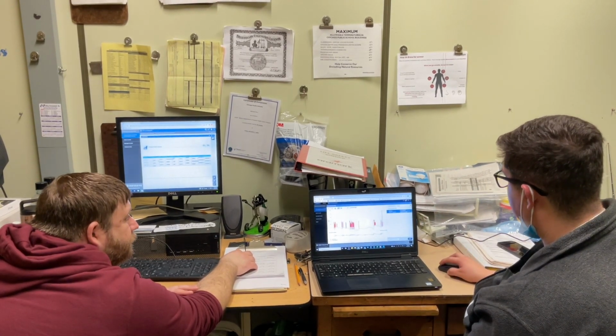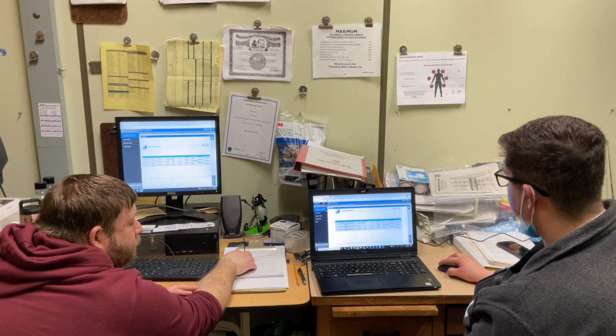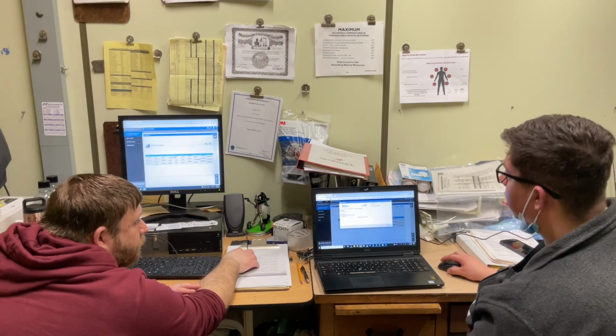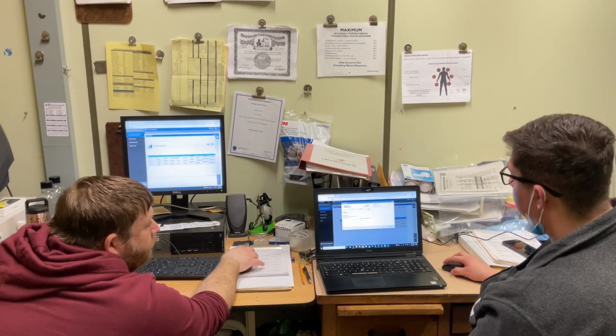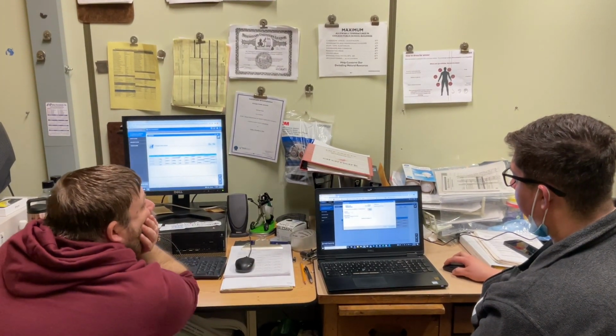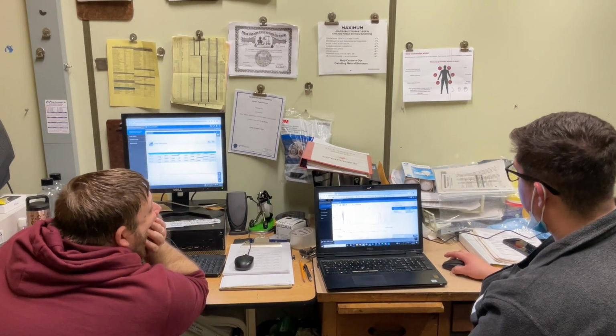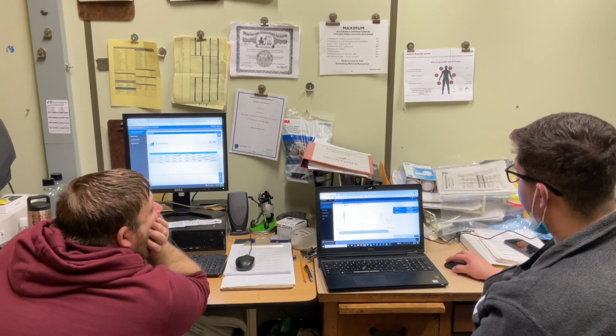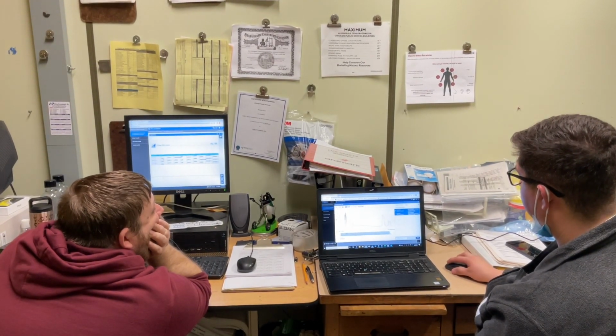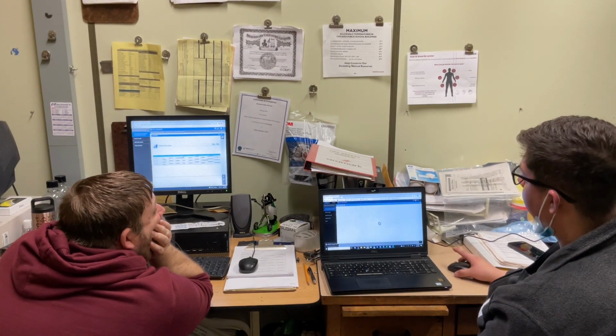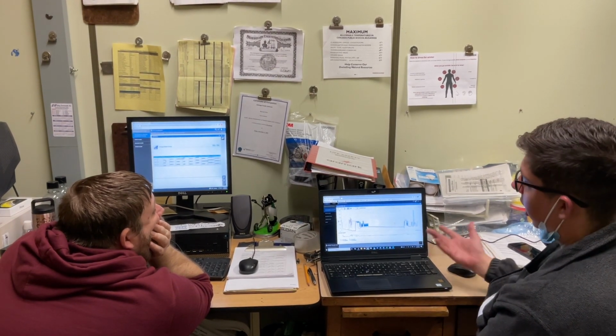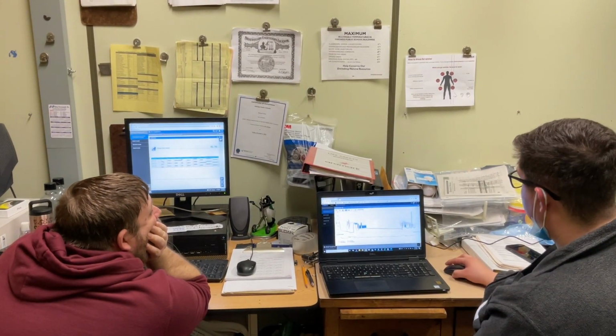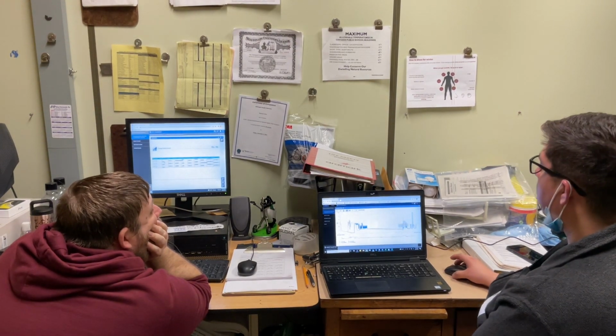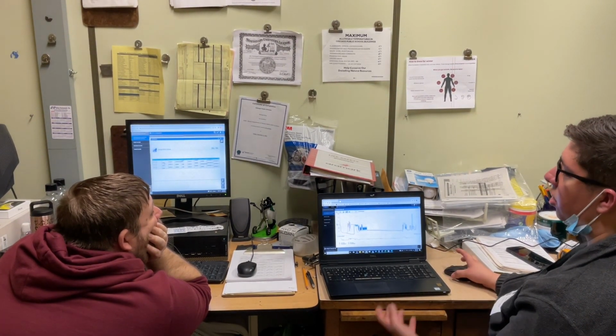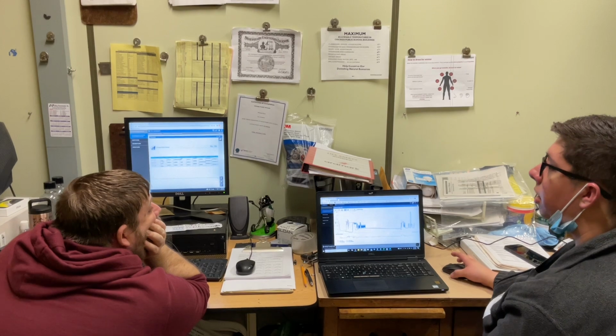So I have this one here - say I exit out and want to compare it to RTU1 supply temp 2. I click on that point, go to trend, and now I have both in this trend viewer. I can select both, hit apply, and layer them together. That's good if you want to check discharge air temp against heating command, things like that.